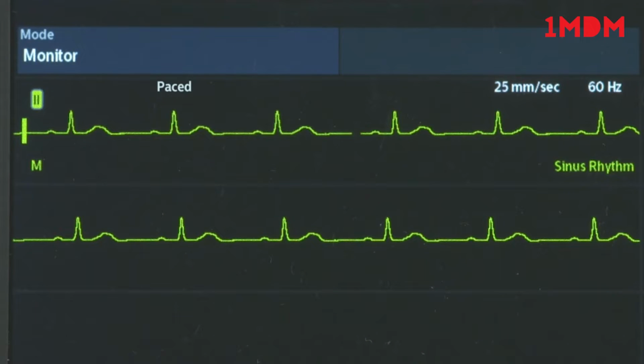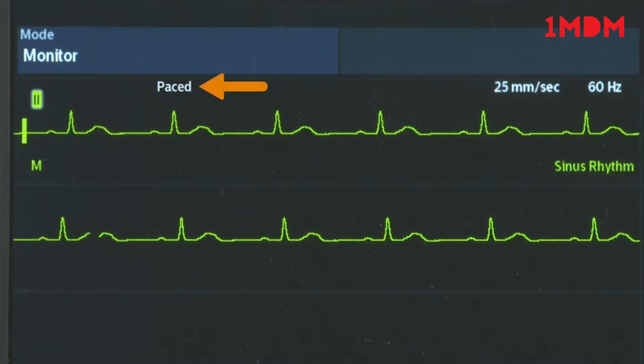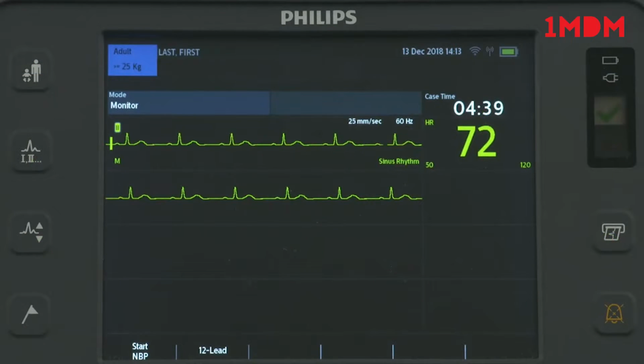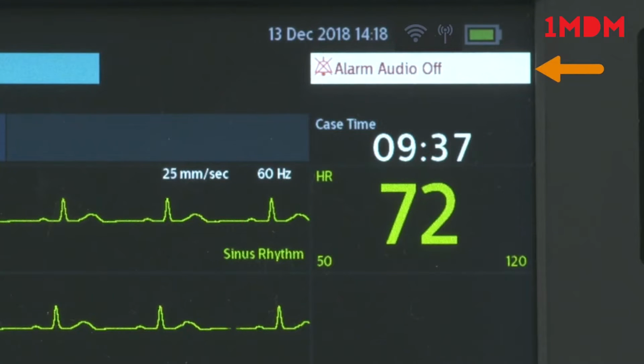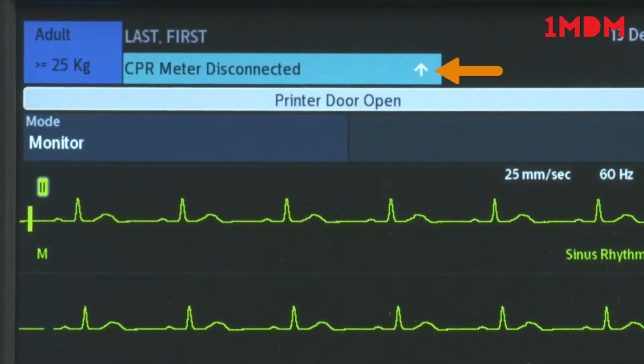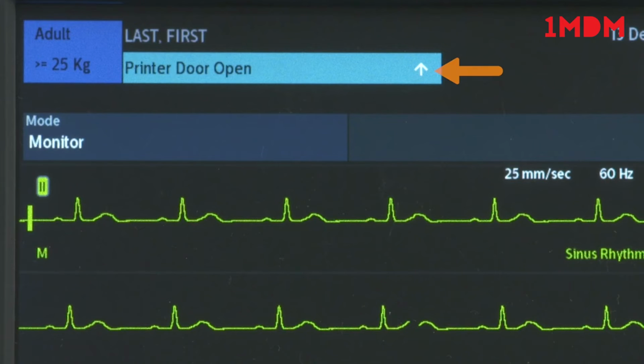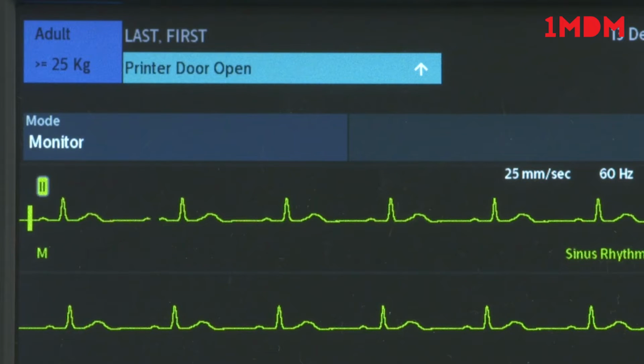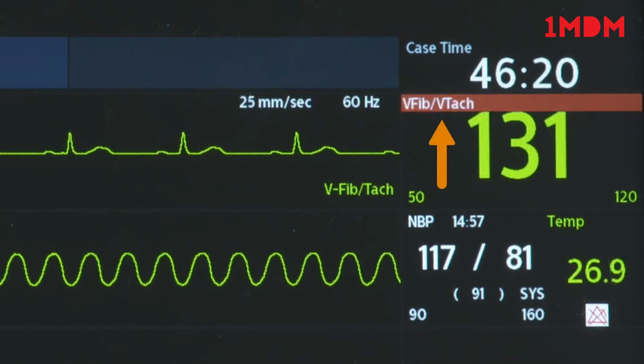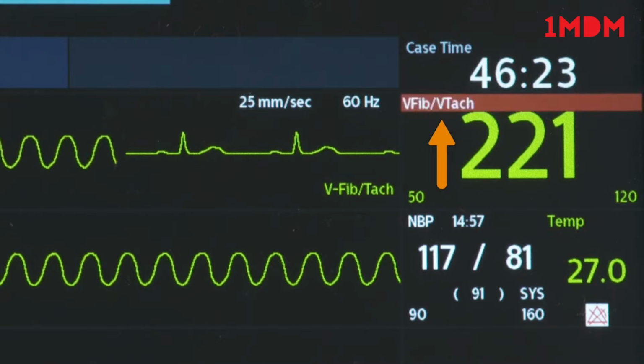All modes, except pacing and AED, display paced status that shows the presence of an implanted pacemaker, if selected. Device information also displays, including the current state of clinical global alarms. When alarms are on and not paused, the indicator is blank. If alarms are off, this message appears along with this icon. Technical alarms indicating an equipment issue appear here. The presence of a white arrow indicates there are multiple alarms. Physiological alarm messages appear next to the patient-related parameter they are associated with.